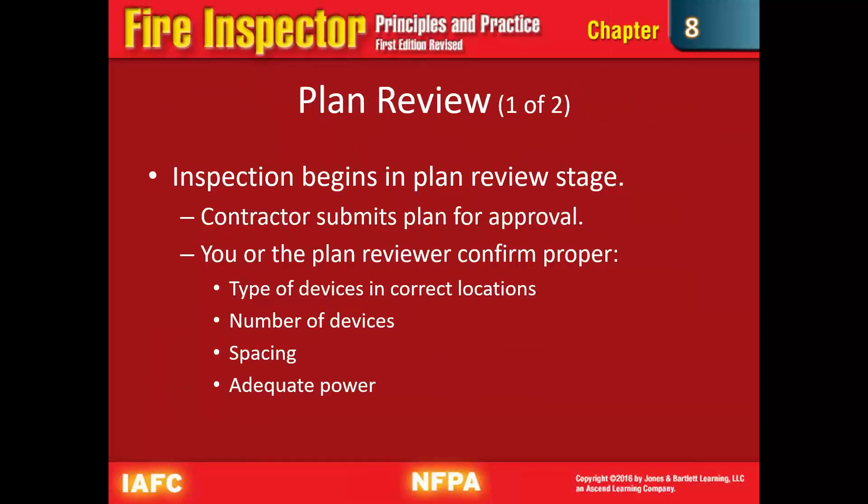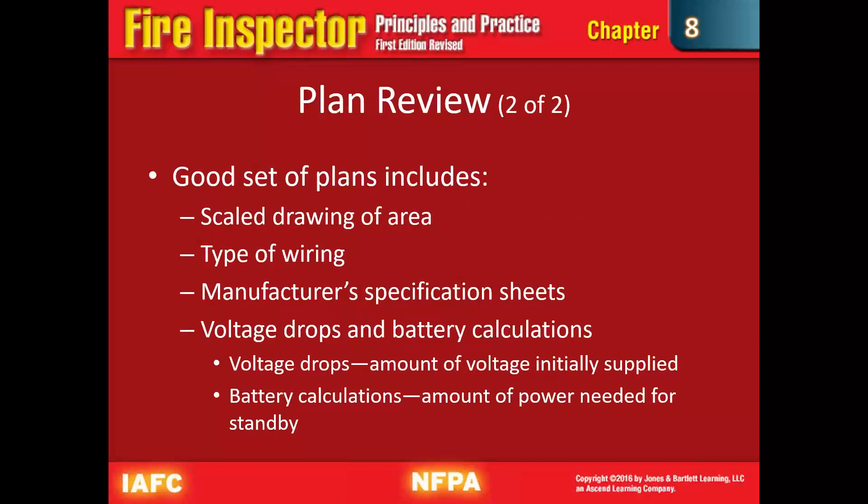Inspection of fire alarm systems begins in the plan review stage when the contractor submits plans for approval. We're going to look at everything, double-check it, and make sure it's suitable for the situation, size, and operation. As the plan reviewer, you confirm the proper type of devices, the number of devices, spacing between heads, adequate power sources, and wiring. You'll also get into how many visual strobes are needed, the required decibels, and all the different factors involved — all of which have to be tracked down in the codes and evaluated with good judgment.